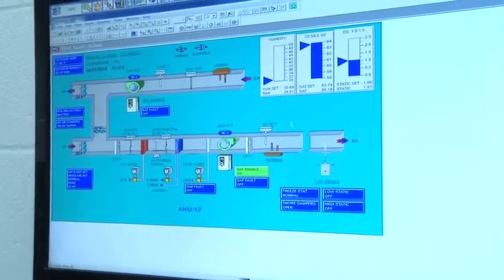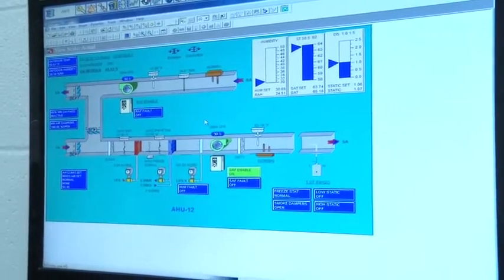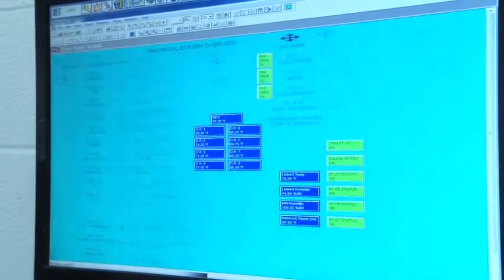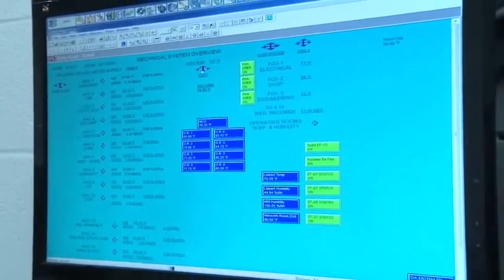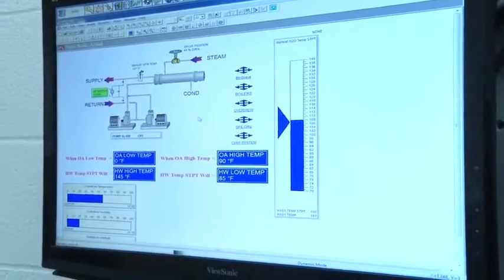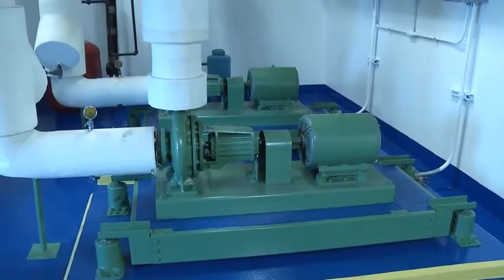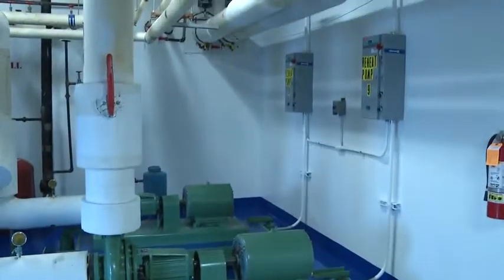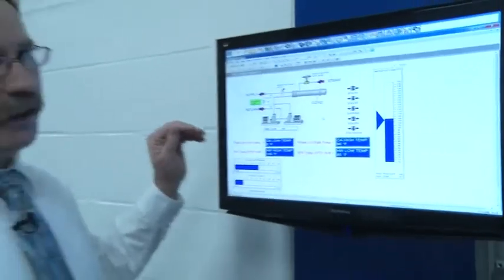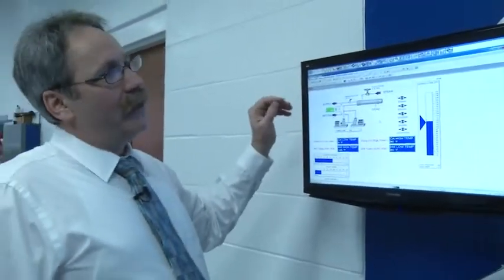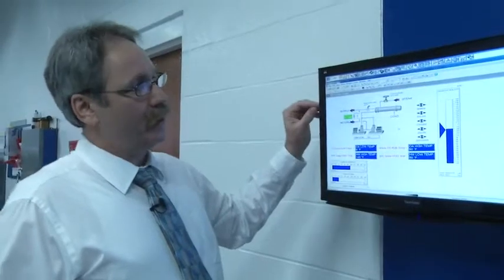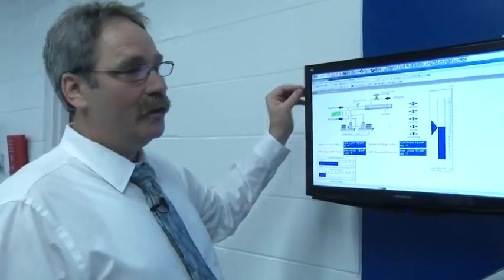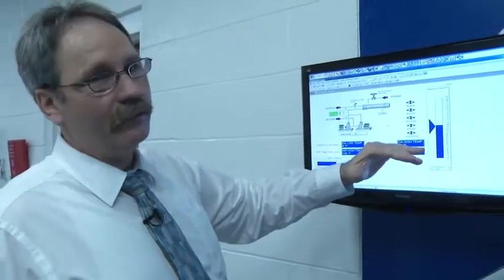All of these points are mapped back — we can look at them with our iPad. This is how we monitor our reheat system. The reheat system is how we heat the hospital. Instead of having a fixed set point, we monitor the outside air temperature, and as the outside air temperature goes up, we need less heat, so that water temperature goes down.